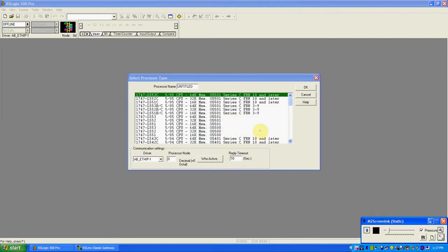You could have clicked on the New tab up here. In the new file settings, there are a few different things that can be done. You'll see that here it's listed as untitled. You can type in any name you want — this is the name the processor is going to have. This is not the name of your program; this is the name of the PLC. If you had 10 PLCs on a network, each would need its own unique name and its own unique address.